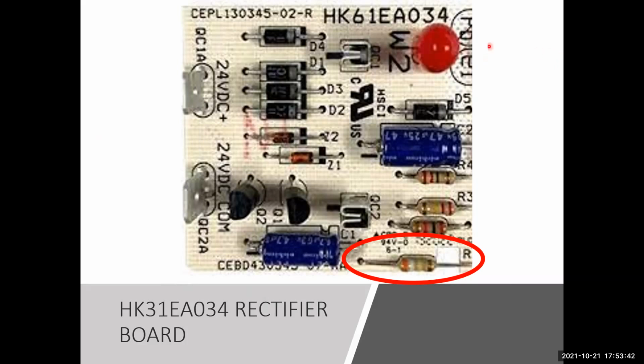So that's your W2, and that's going to be your 24 volts AC, converts to DC right here. If we want to jump to another board, we're going to go off here with the positive and our negative. And then we talked about the jumper. You can see that there's a little notch over here. It's going to be a lot easier to cut. And you cut this to get an extra 3 seconds to make it a total of 8 seconds. Uncut, this board is 5 seconds.